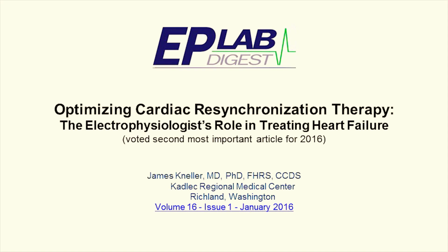And it's also a topic that we take very seriously, and we've published on that in 2016 an article on how to optimize those devices, because how you program the thing is everything. Just putting it in and leaving it is wrong. You have to pay attention to how it works and how it's capturing the heart electrically to get the benefit. And we wrote an article on how we should be doing that in our device clinics in a way to get the most bang for the buck.